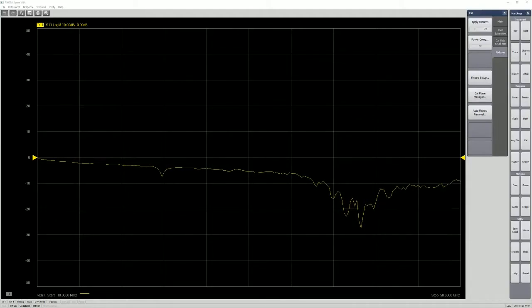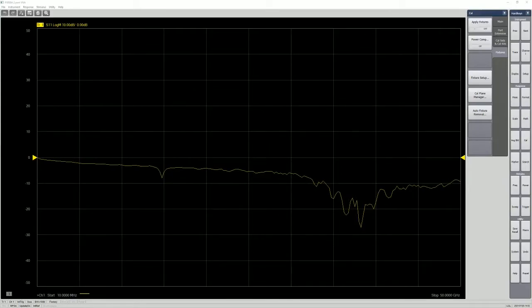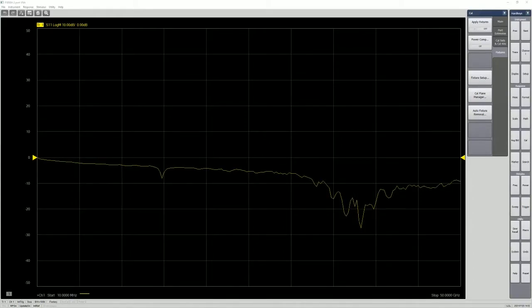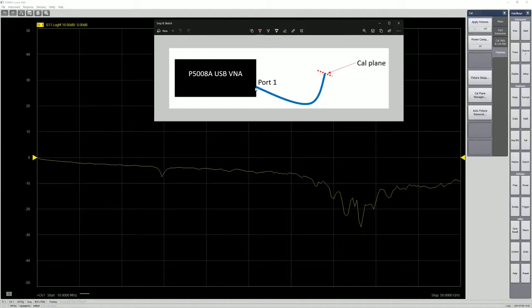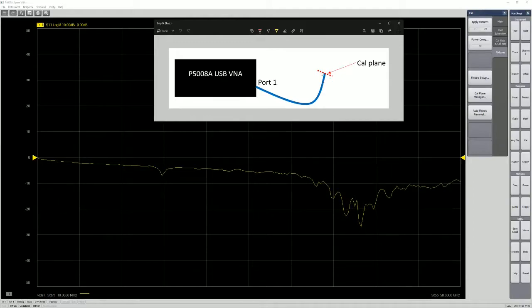And so what you're seeing right now is connecting it to a P5008A USB VNA and this is my setup. So I have a P5008 USB VNA and I'm using port 1 and this is my cable. The blue is my cable and this is my calplane.